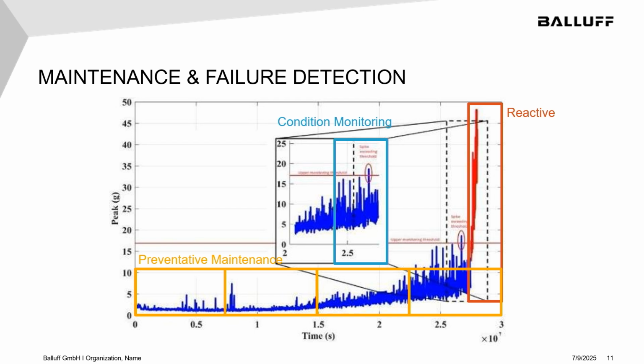The other thing that's important to note is that we had several spikes that almost exceeded that alarm level, but probably didn't. And so setting that alarm level is a little bit complicated. You can do it based on experience with the machine, but there are also ISO standards available to help guide you, and there are other experiences that you can use to set that at the right level. So perhaps in this case, if they'd set it a little bit lower, they would have probably had almost a month's worth of warning ahead of time that that failure would occur.